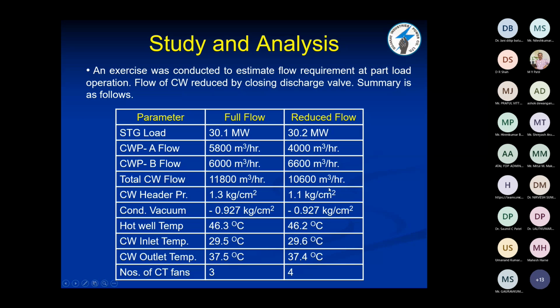The summary is as follows. Now you can see from this slide. This is the parameter, this is at the full flow, and this is at the reduced flow. Now, the STG load is 30.1 megawatt. When we reduce the flow, the STG load remains the same, that is, generation remains the same. But the flow of cooling water pump A was 5,800 meter cube, now it has come to 4,000 meter cube. At the reduced flow, the generation is the same. That is, the excess flow of cooling water is going to the condenser.